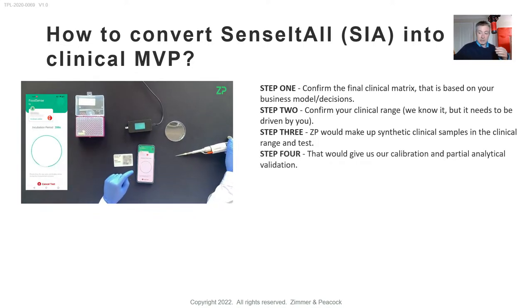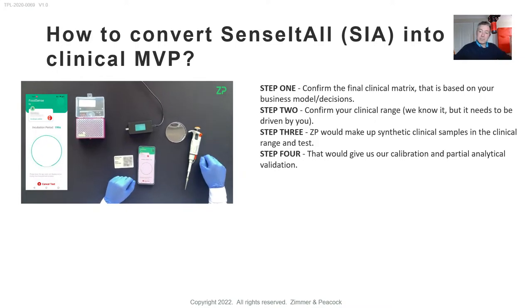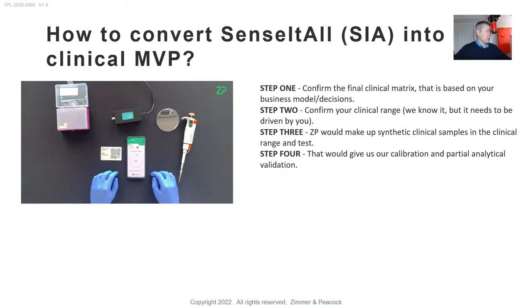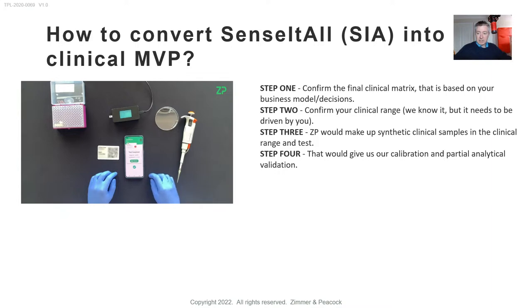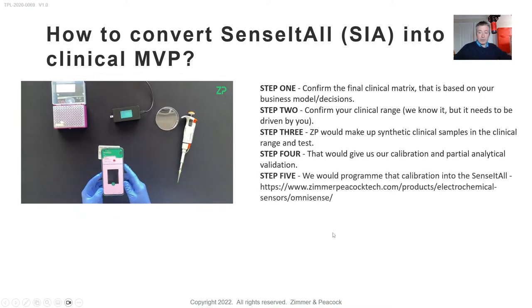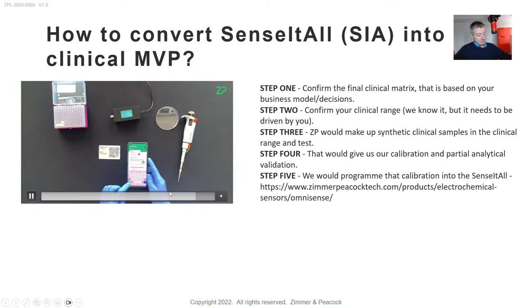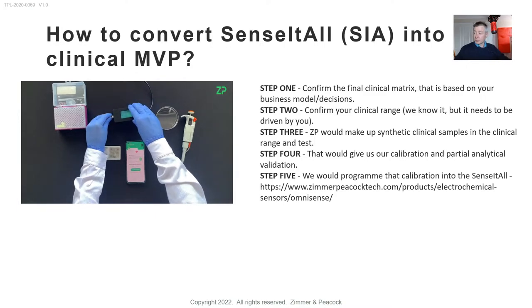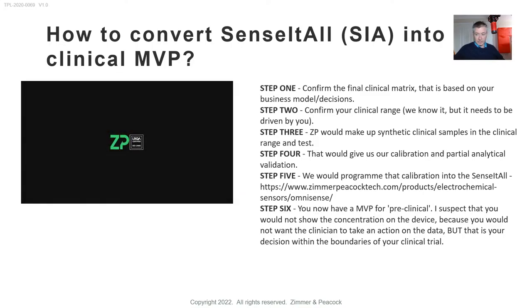Testing the synthetic samples gives us essentially our calibration curve and partial analytical validation. I say partial because we are ISO 13485, and full analytical validation means something quite significant — thousands of hours of work. We then program the calibration into the SensIt All platform. By step six you actually have your pre-clinical device and can go into your pre-clinical studies, at which point we're keen for you to get into a clinical setting and start testing real-world samples.